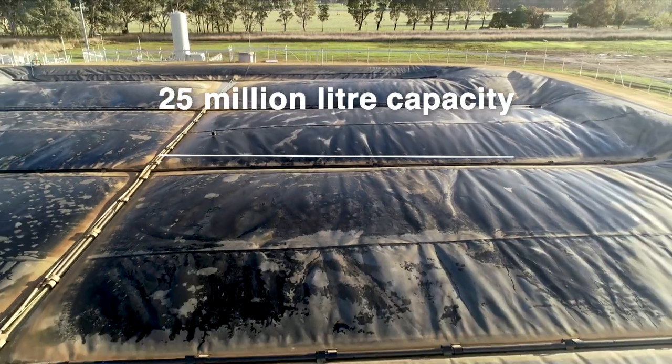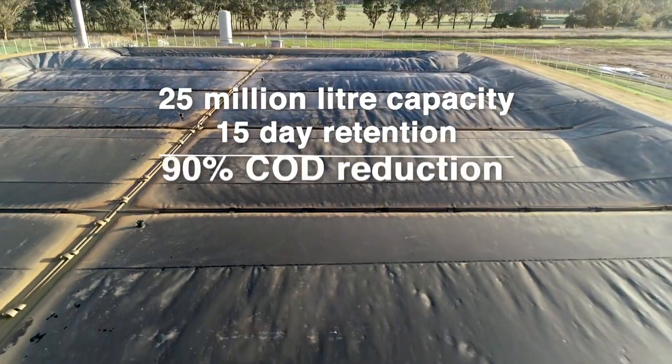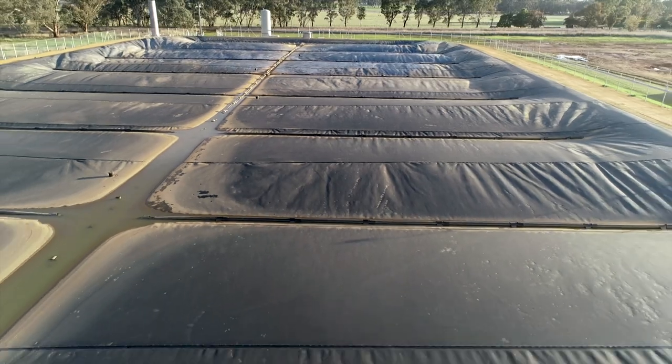This is the first time that Tees will utilise biogas from a covered anaerobic lagoon (CAL) for fuel in a co-generation plant. The new CAL is 25 million litres and has about a 15-day retention time. Across that period we hope to achieve about 90% COD reduction, meaning maximum realisation of the biogas yield without wastewater loss.